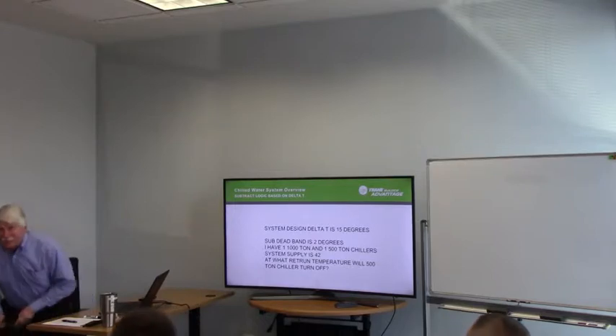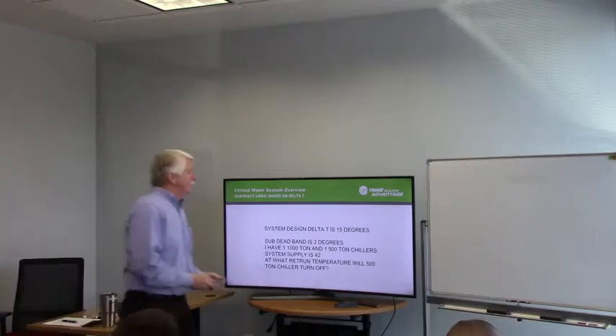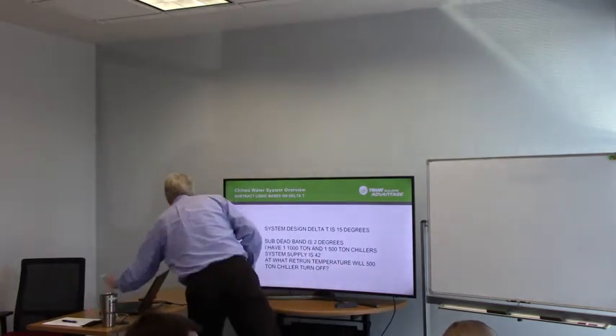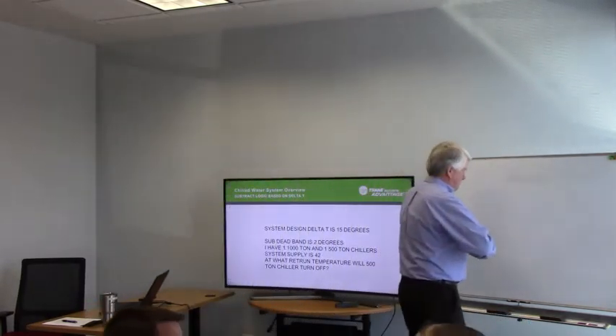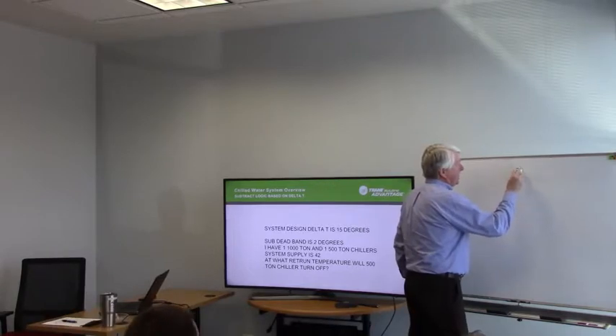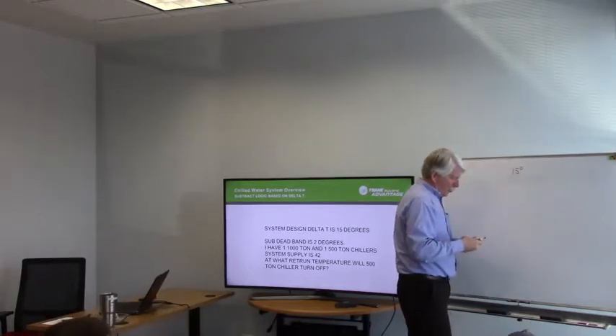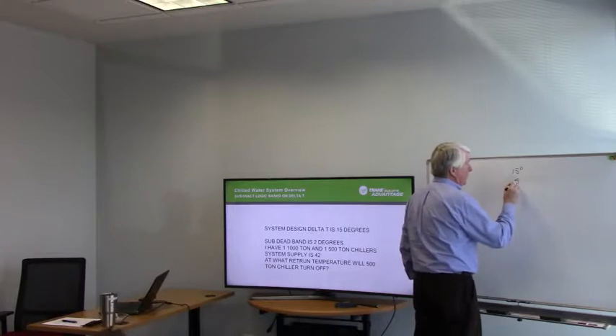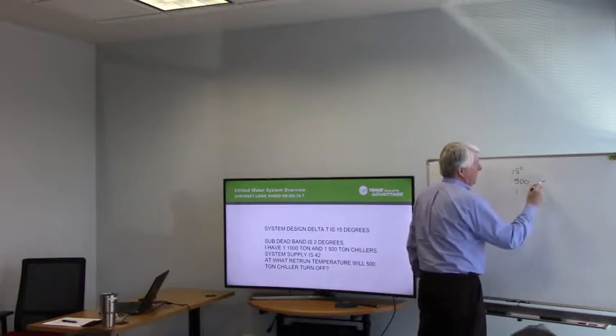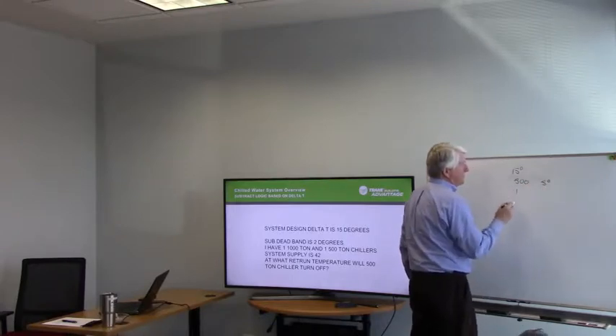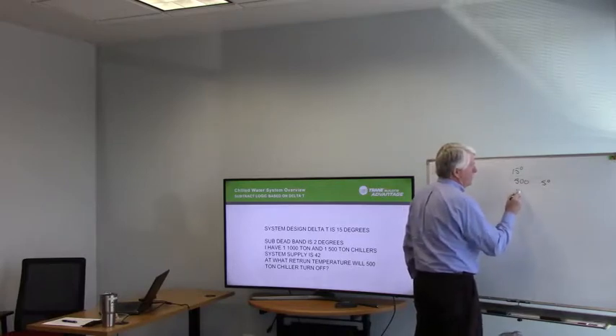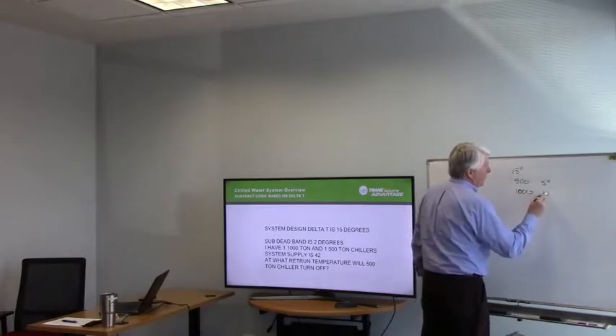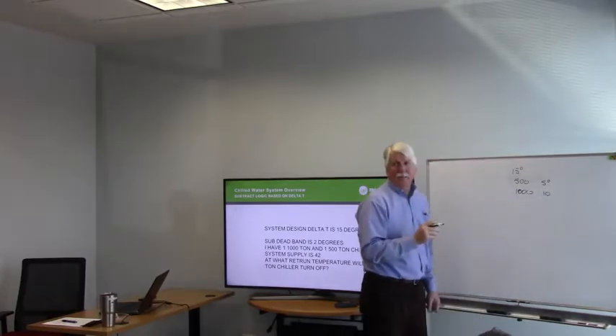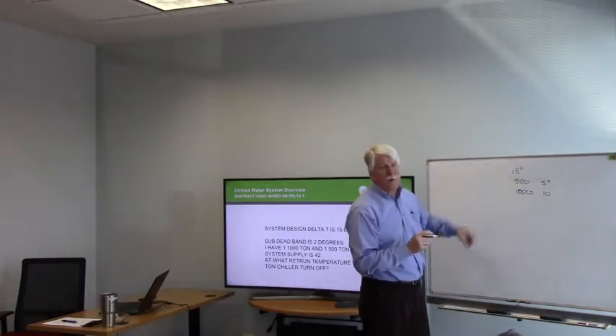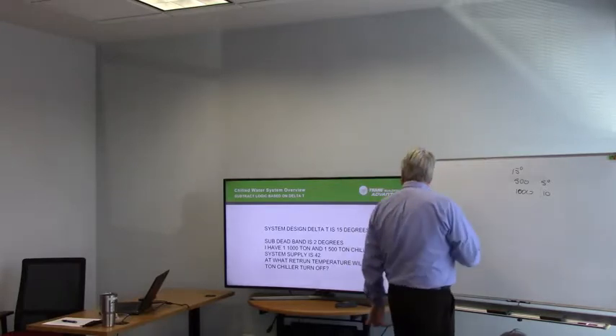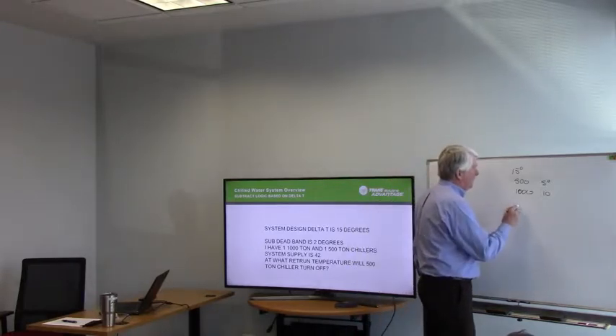Okay, let's do the math. Looking at it, I got a 15-degree delta T, right? How much work will the 500-ton chiller do? 5. 5 degrees. How much work will the 1,000-ton chiller do? 10 degrees. Okay, now I've decided in my chiller sequencing, this is the one I want to turn off. So I've got 15 degrees and 42.